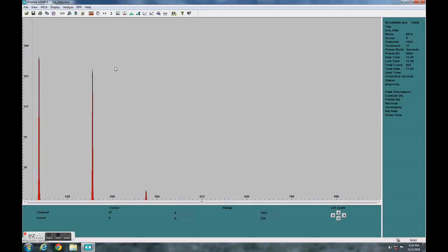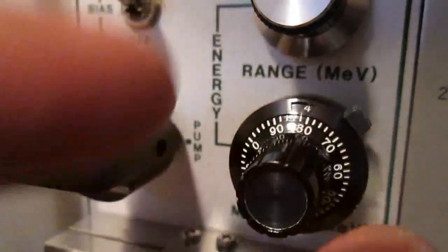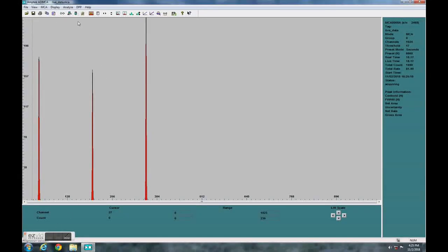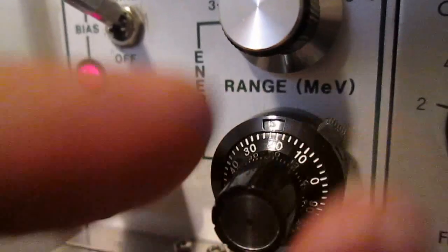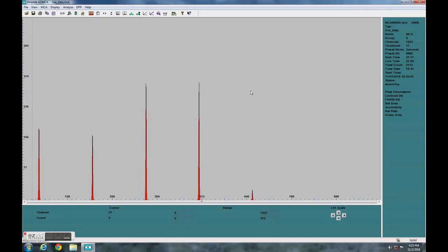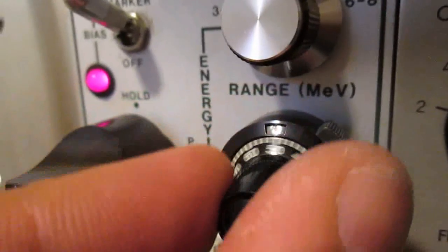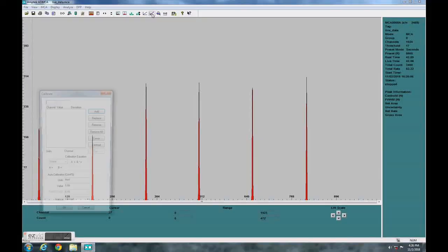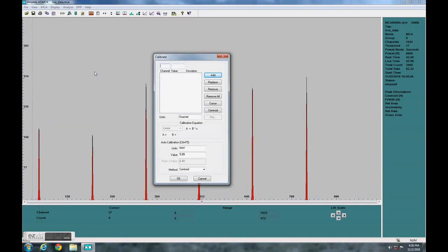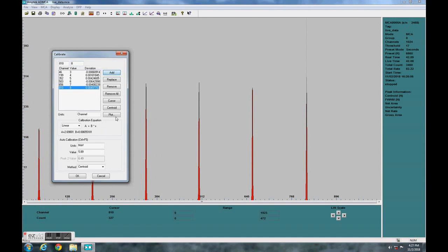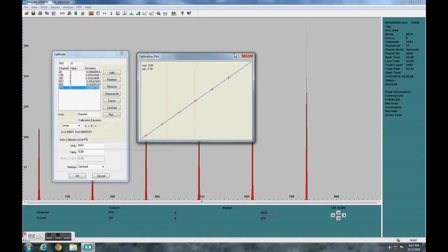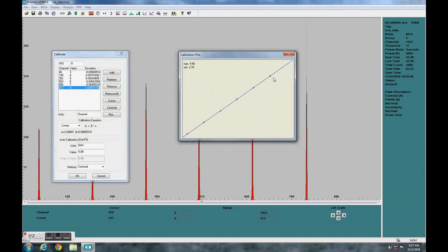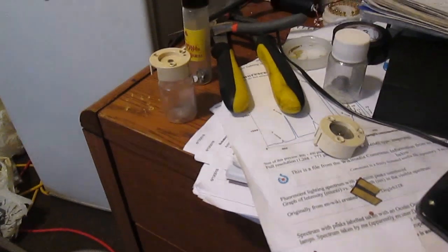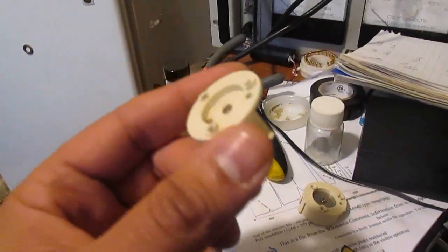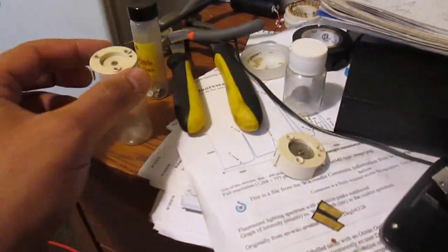Now, most working alpha spectrometers have a pulse generator that allows for calibration. And this is done by simply matching the voltage generated by the pulse generator to a specific energy from a particular voltage from the incoming alpha particle, thereby creating a linear calibration curve that we can use for further analysis of unknown samples. My first obvious pick is the americium-241 from smoke detectors.